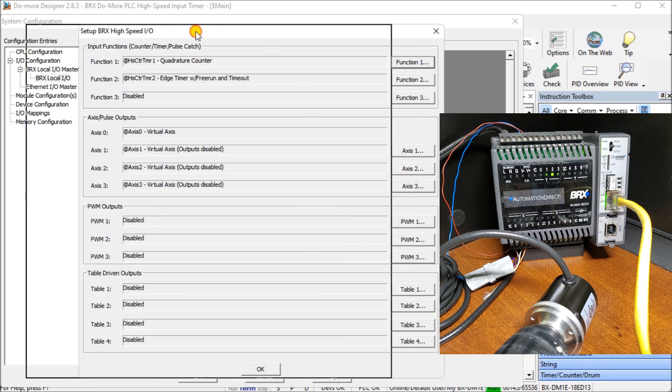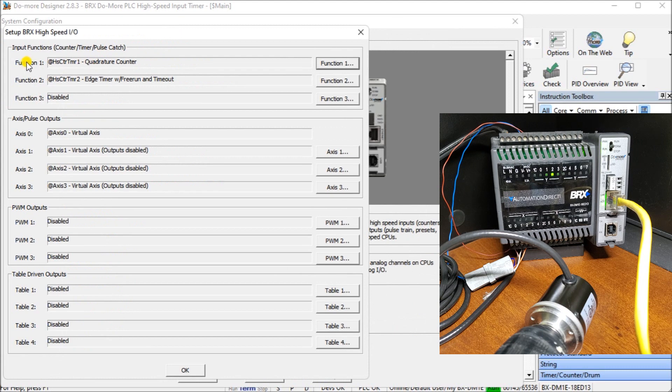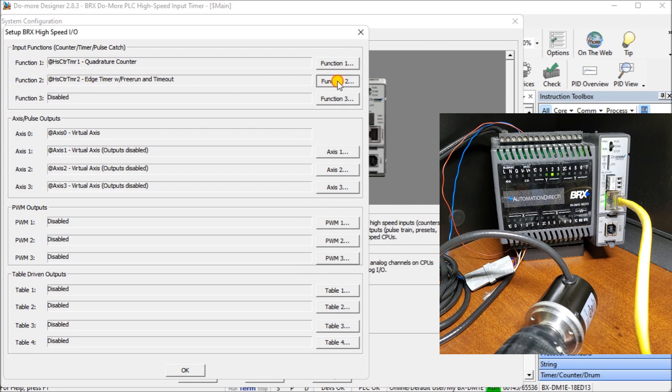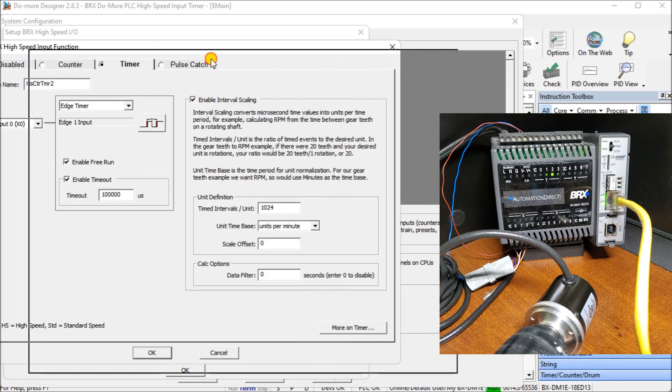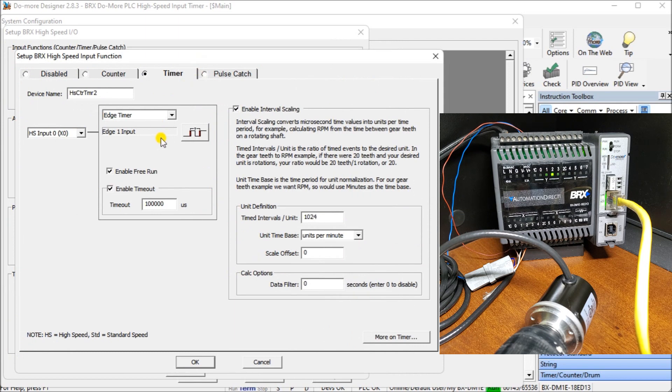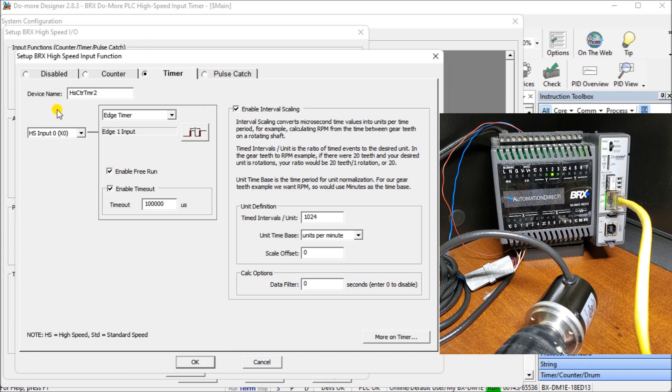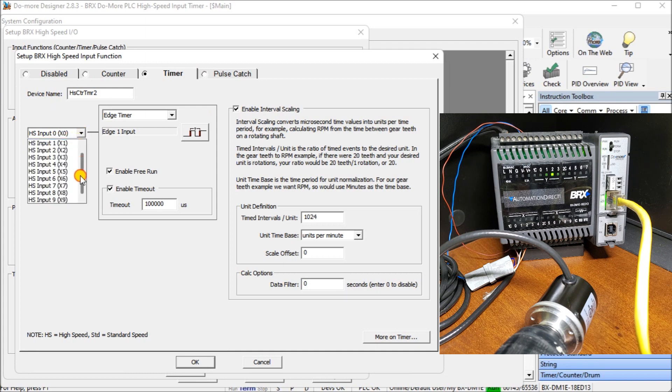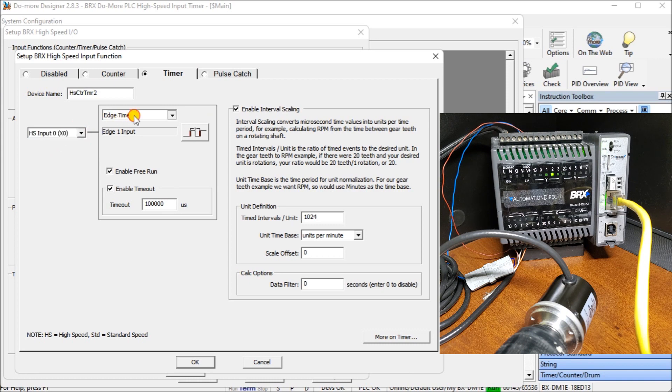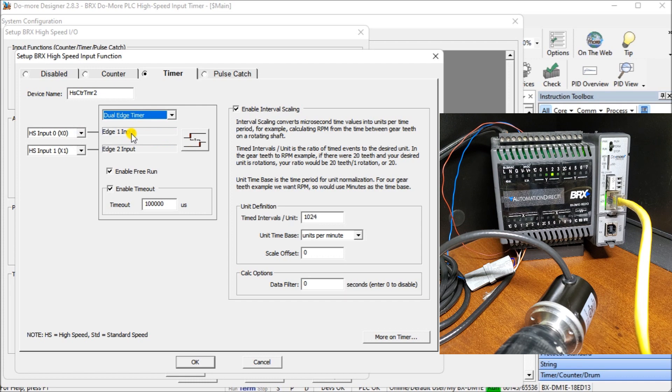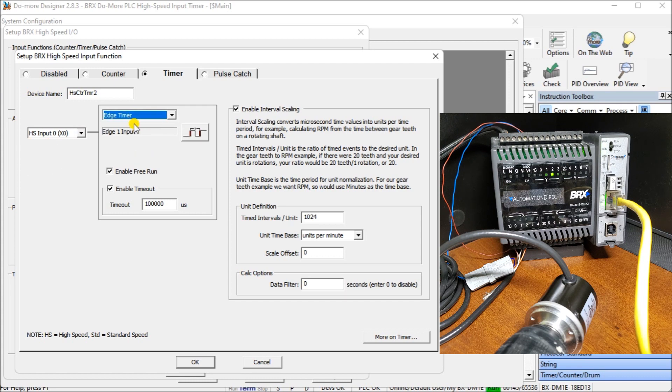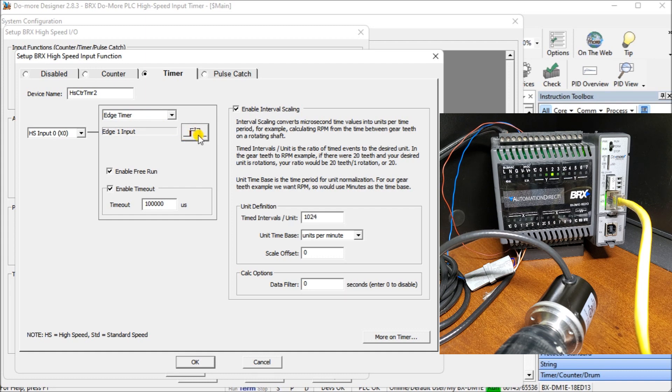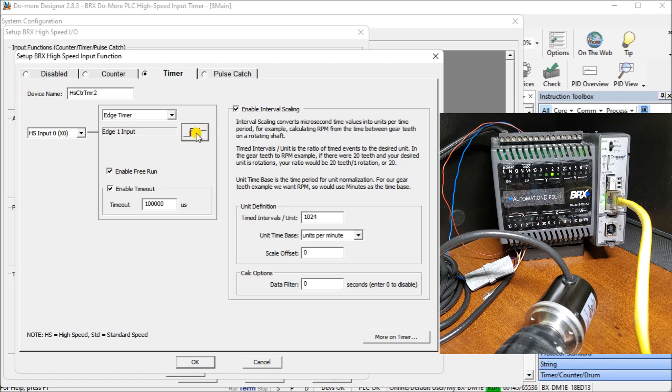Once we do, you'll notice we had function one that we programmed before, and now function two, which is going to be my high speed edge timer, we'll program it. Going into the edge timer, we have our device name. This device name will start up and give you all the parameters. It defaults to high speed input zero, but here it will list all of the available inputs that I have for this PLC. Then I have my edge timer here. I can also have a dual edge timer, and I have a second one come in. We're going to use just the one. The edge input will be on the leading edge. I can also go on the leading and trailing edge or trailing edge to trailing edge. We're going to go on leading edge to leading edge.